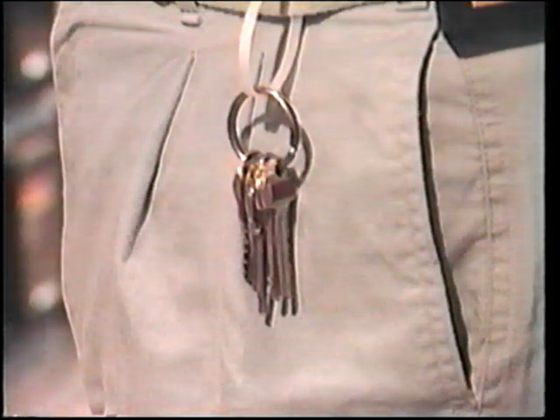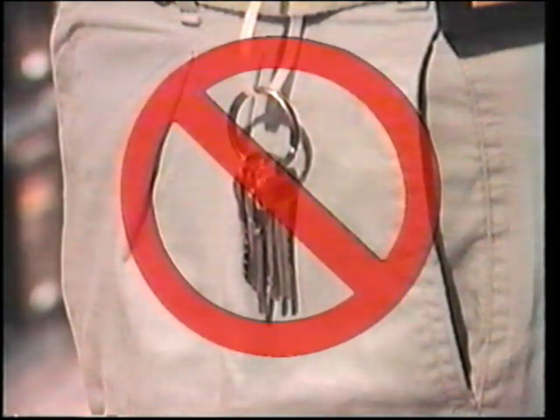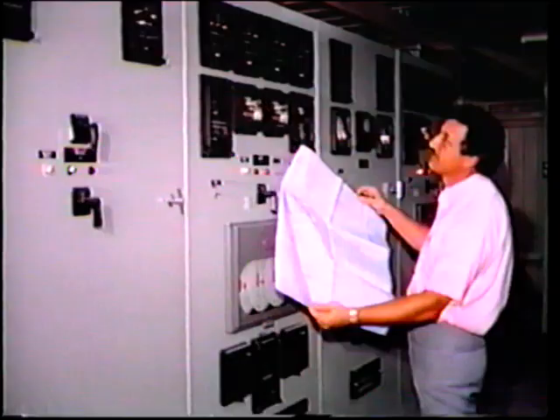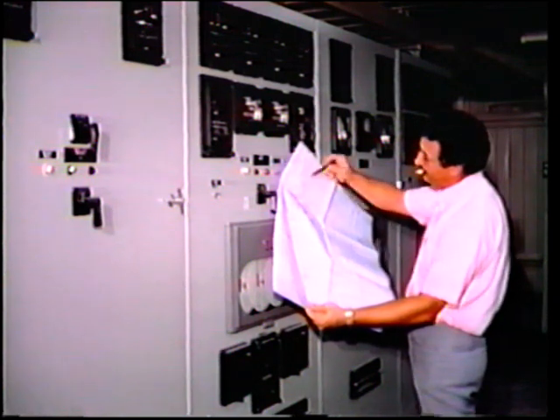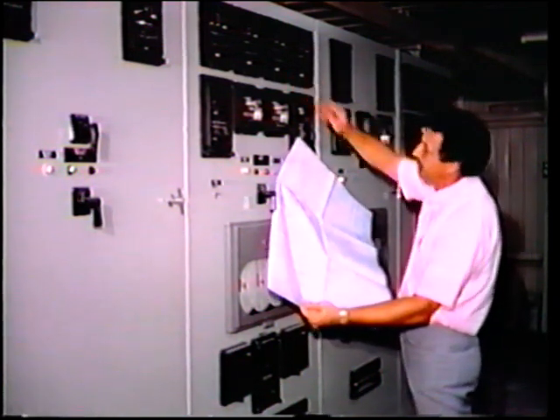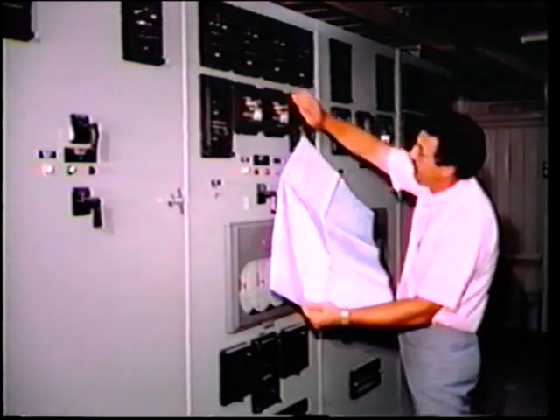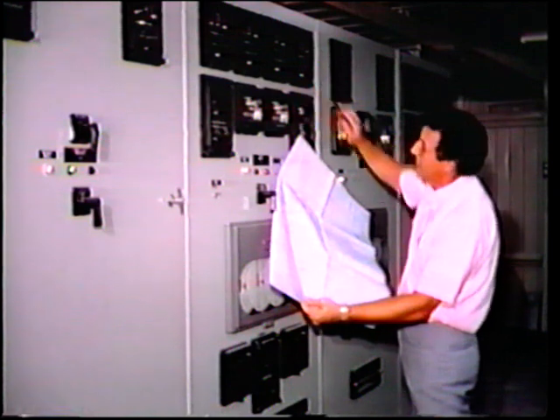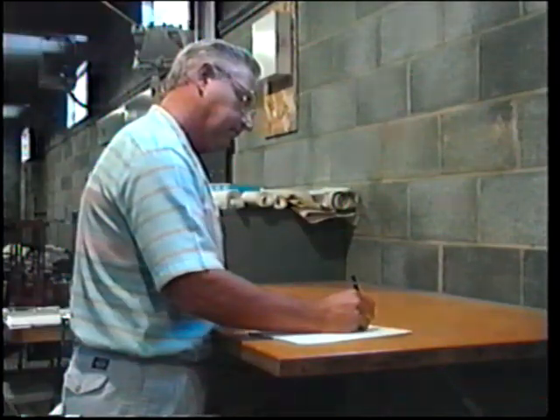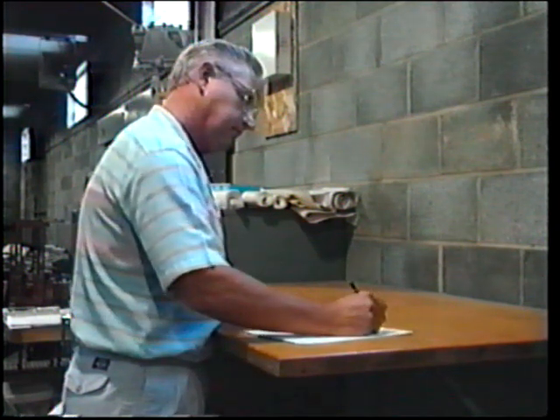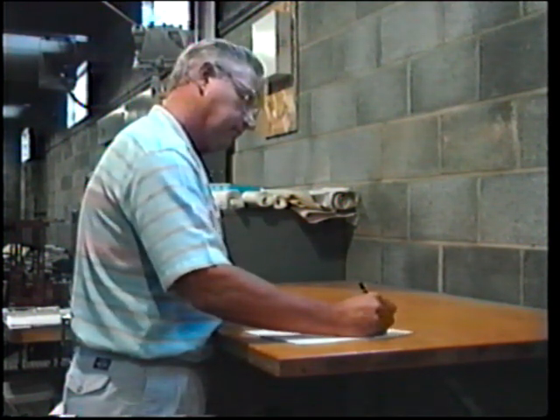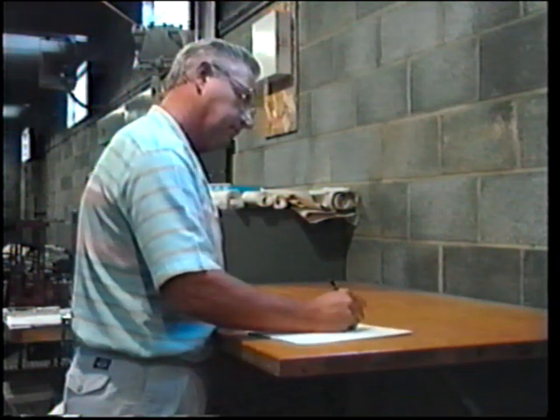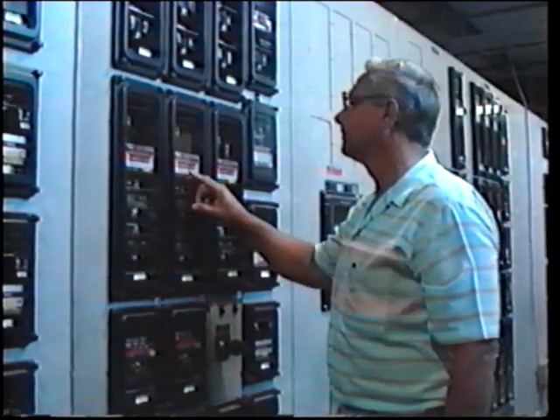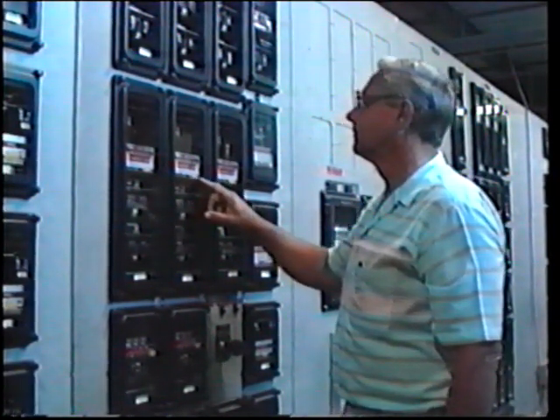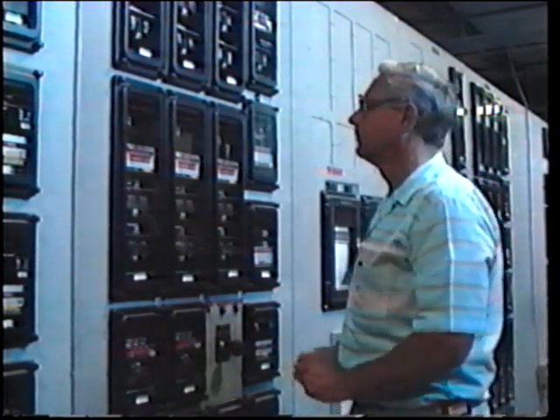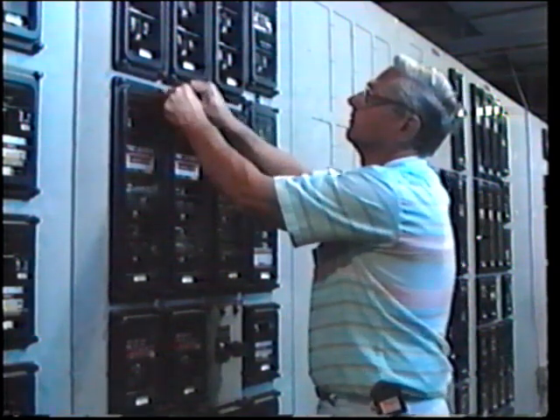Also, and I am sure I have no need to repeat this, never wear metallic objects while you're working on live equipment. Identification of equipment is vital. You must always make sure that you are working on the right equipment and that this corresponds to the schematics and diagrams. Good work planning is vital so that you know precisely what needs to be done and how to go about it. Most companies require that the technicians fill in a job procedure form before commencing work. This includes the objective of the work, isolations required, and each of the major steps to be performed. Always check and double-check all panel and relay nameplates before starting work on a relay. It is also a good idea to tag all adjacent equipment that is not to be operated.